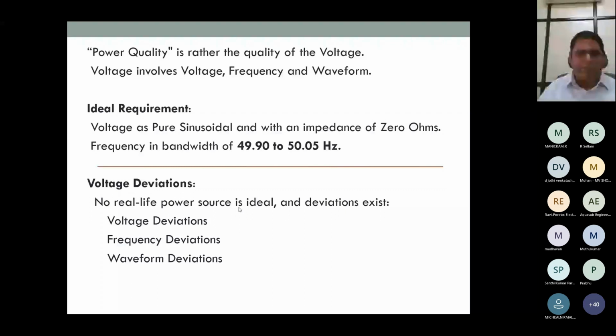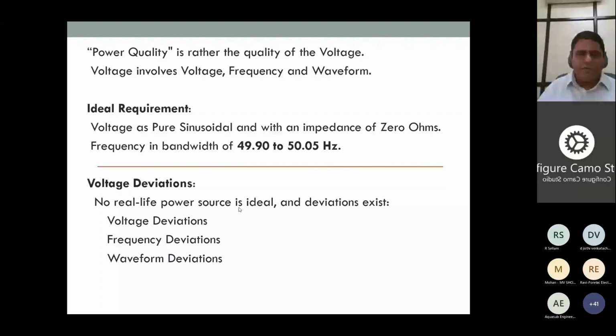So what we expect from an electricity board is a pure sinusoidal waveform, voltage as a pure sinusoidal wave, with an impedance of 0 ohms. We also need a frequency in the bandwidth of 49.9 to 50.05 hertz. This is what is expected, but as every one of you knows, we don't get such a waveform in a real life scenario, and the deviations exist. The deviations are voltage deviations, frequency deviations and waveform deviations.